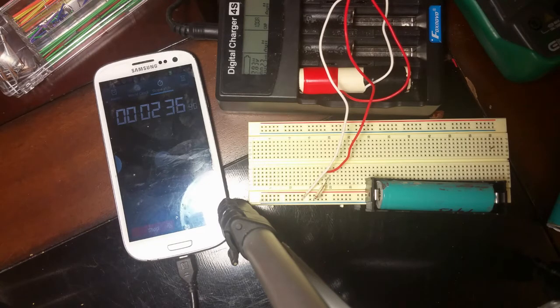So if you do not have the correct fuse on each of the cells, even when the BMS shuts off the battery, if you've already lit the fuse, take an example of a sack full of firecrackers. You light the fuse on one and drop it in that sack. There's no getting that firecracker out of the sack, and it's going to probably damage or set off a chain reaction with the other batteries.